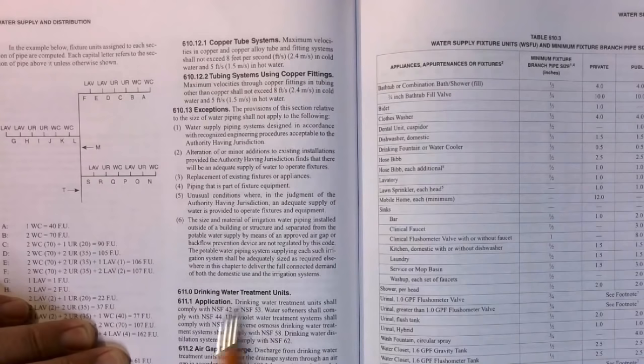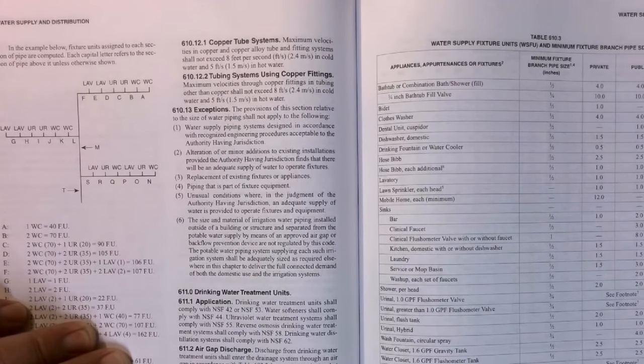Depending on the system that you use to treat your water is the different standard that you have to deal with. Air gap discharge. Discharge from drinking water treatment units shall enter the drainage system through an air gap in accordance with Table 603.3.1 or an air gap device that complies with 603.2, NSF 58, or IAPMO PS 65. And again, Table 603.2 was that whole air gap distribution table that we talked about earlier in the other video.